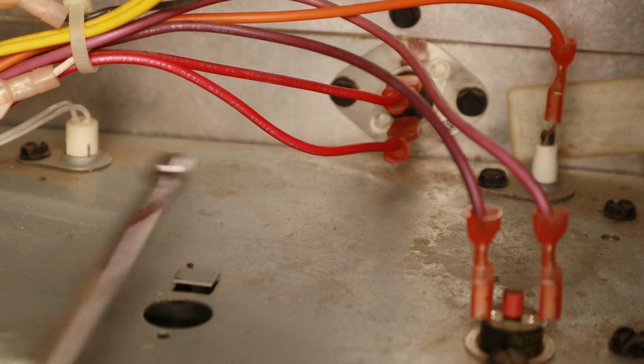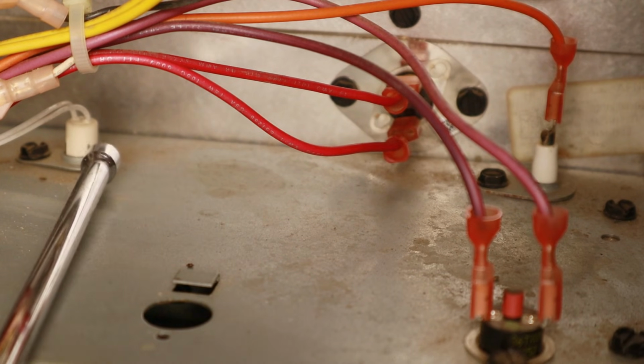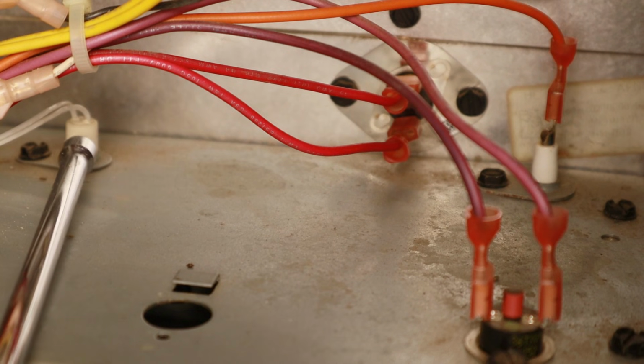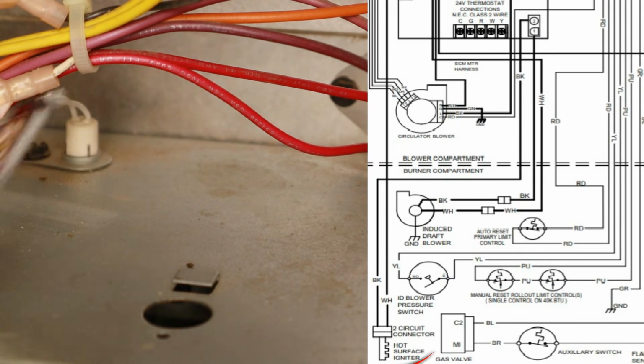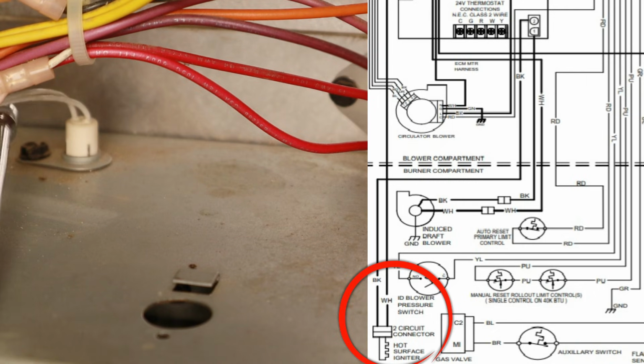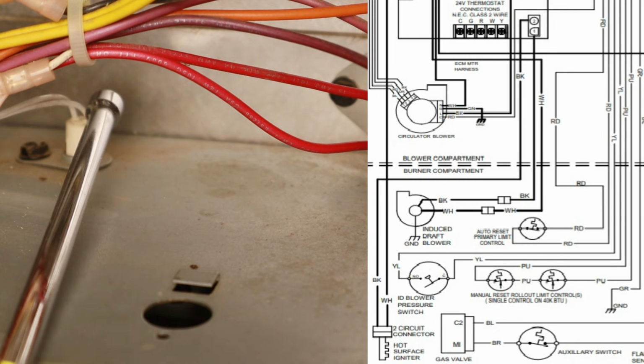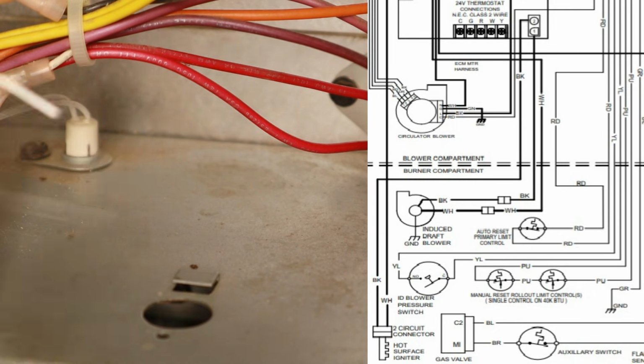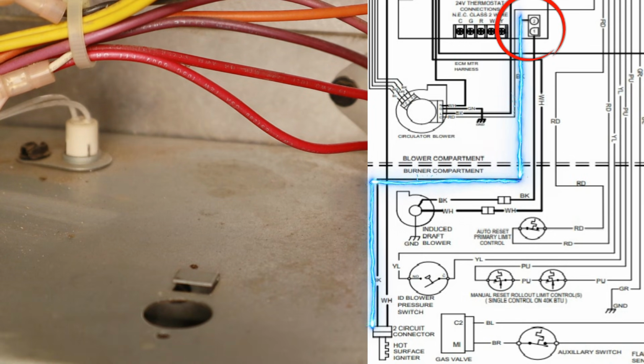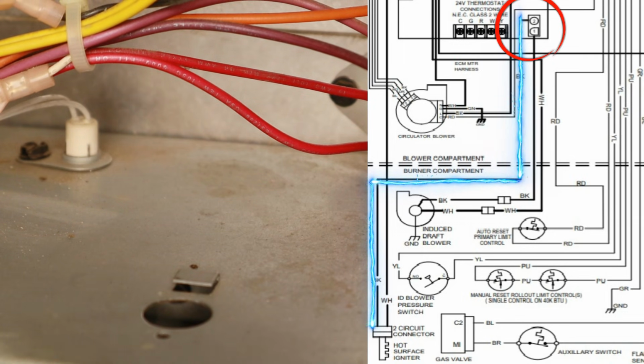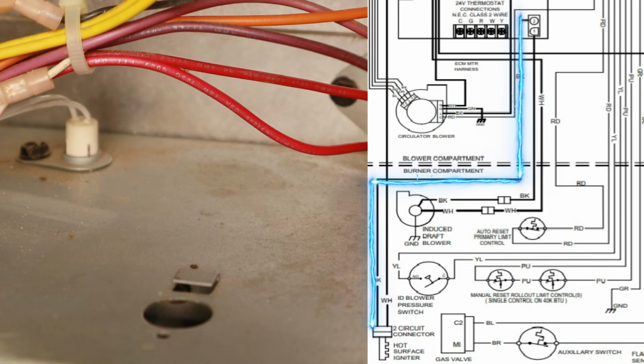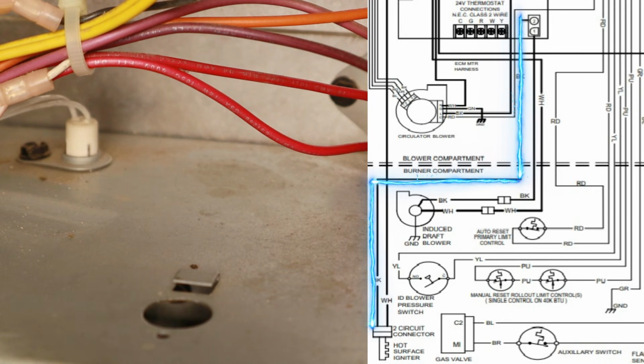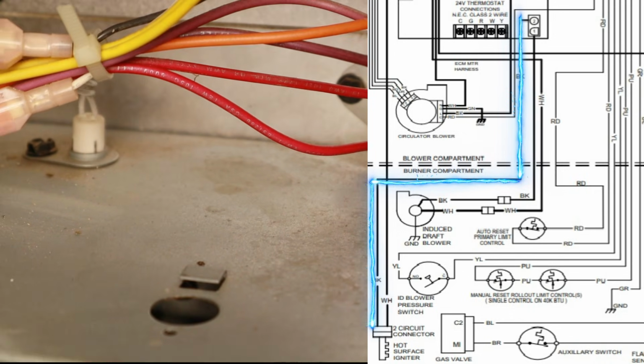You can always tell which one the hot surface igniter is, because our hot surface igniter is high voltage. When we look at our schematic, that is going to be two wires, a black and a white. And as you can see here, we have two wires going to this probe. When we go back to the schematic and find our hot surface igniter, we find that its wiring goes back to the same Molex plug that our inducer motor is plugged into. So that little Molex plug in the corner of the control board should also be sending out 120 volts to our hot surface igniter so that it will begin to glow.